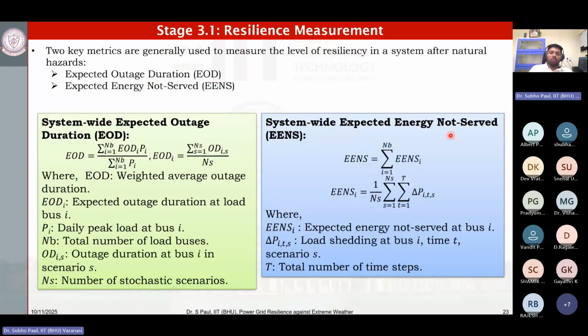So to measure this resiliency level, normally two different resiliency measures are calculated and reported in the reports. The first one is the expected outage duration. That means for an event, if it passes by, what is the duration? That may be what I told at the very beginning, that it is taking 2 to 3 days. So that is your duration time. And the second is the system wide expected energy not served. That means, let's say your energy capacity is 30 gigawatt and you have cut down almost 20 gigawatt, then your system wide expected energy not served will be very high. That measurement will be very high. So we always want this expected outage duration to be as low as possible, and the energy not served also as low as possible. If these two things are low, that means your network is a resilient network.